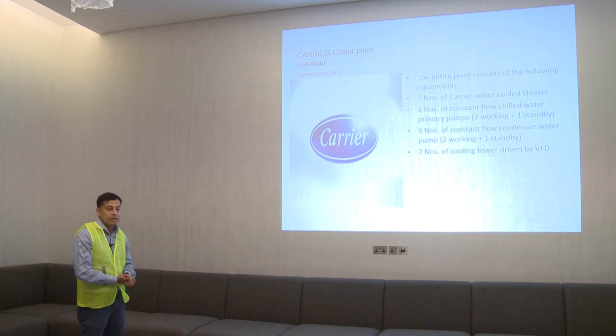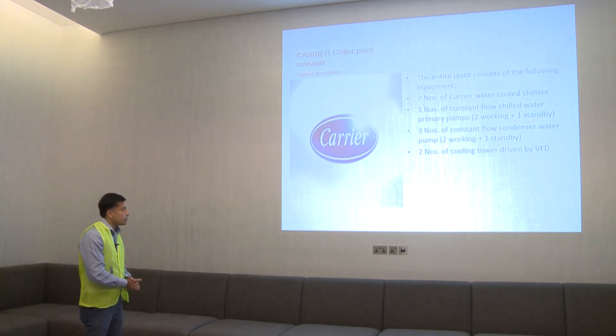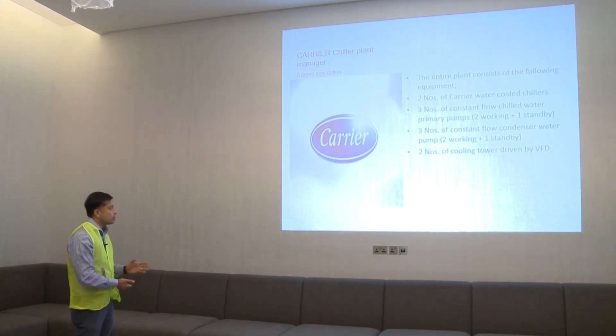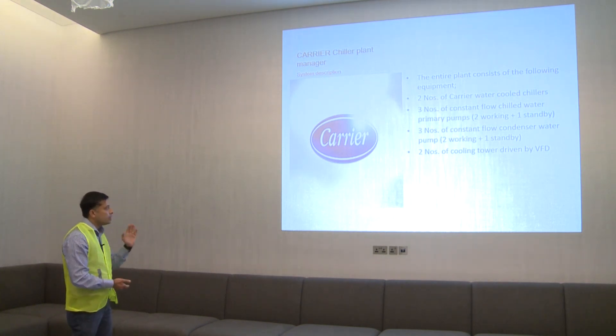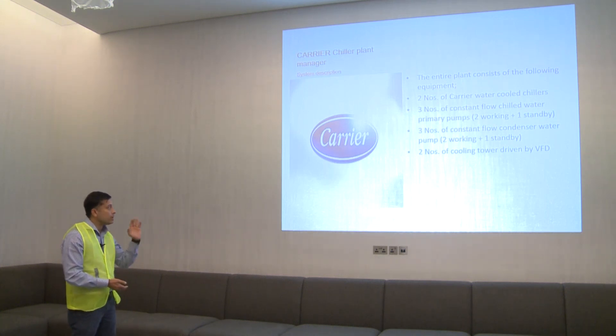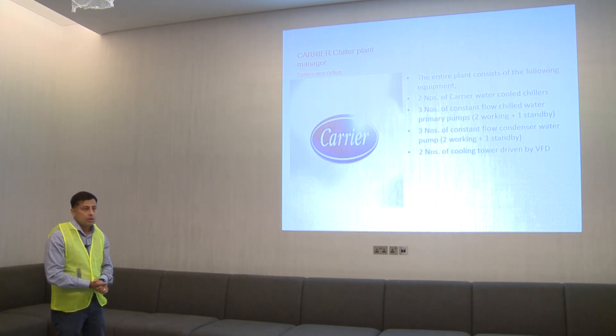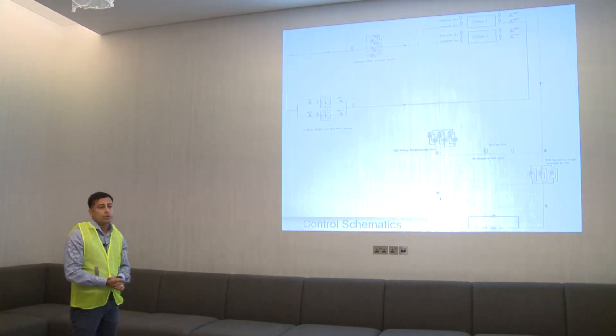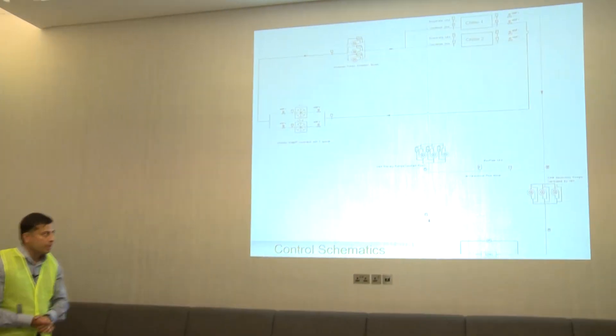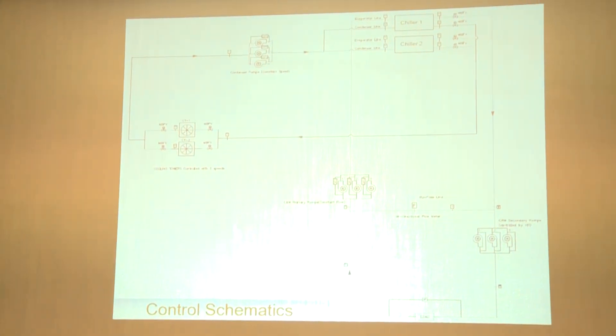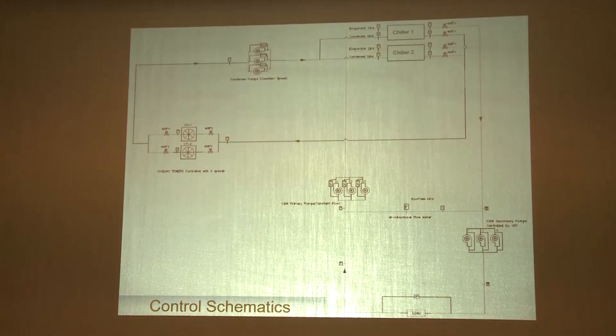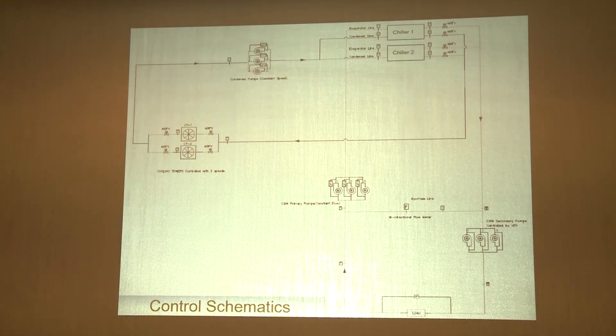We have two water-cooled chillers, three constant-volume primary pumps, and three constant-volume condenser pumps — two working, one standby. Primary pumps are also two working, one standby. And two cooling towers. These are the equipment we are going to control from the Chiller Plant Manager. All the equipment in the cooling system is controlled by our Plant Manager.